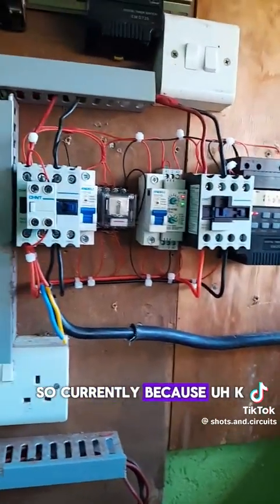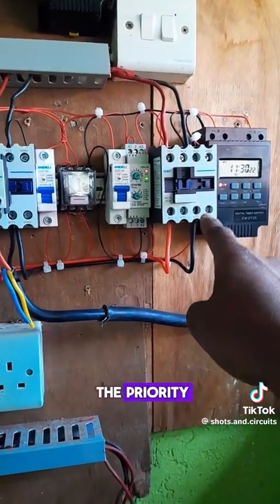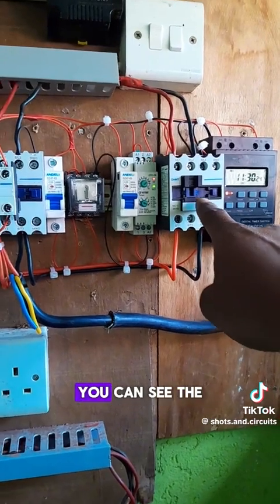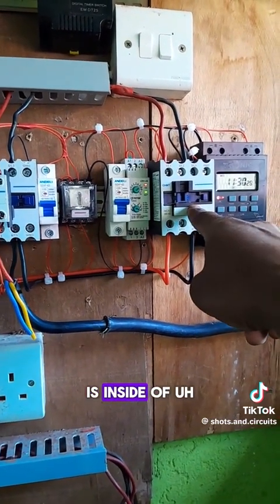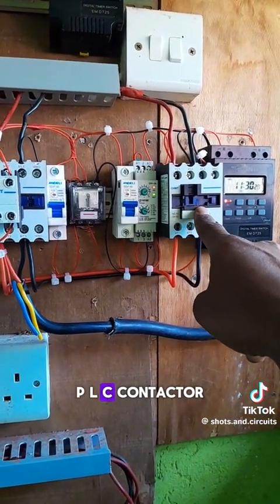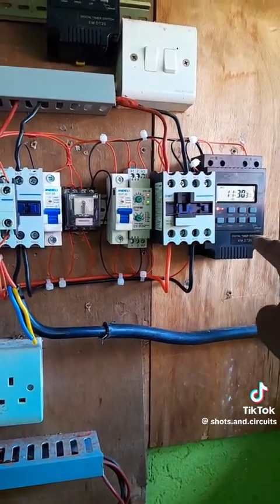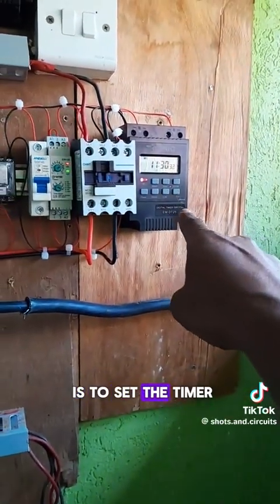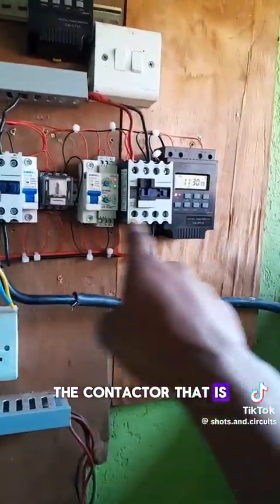Currently, because KPLC is the priority, you can see the coil is inside this KPLC contactor. So we want to set the timer so that, because it is during the day, the contactor being used is the solar backup contactor.